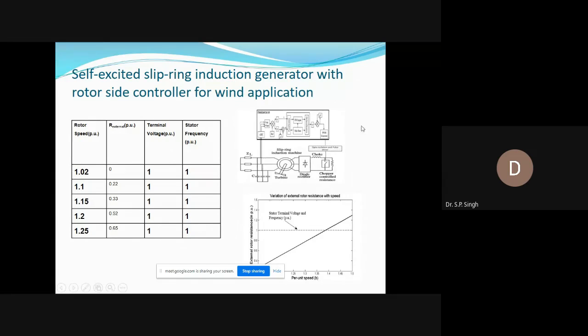So this scheme is capable of controlling the voltage and frequency during speed, over the speed range beyond synchronous speed. The speed range beyond synchronous speed is decided by the rating of the rotor as well as the load resistance. Suppose you increase the value of the load resistance, you can increase the operating speed of the generator. So here we have given the result for getting constant voltage and constant frequency.